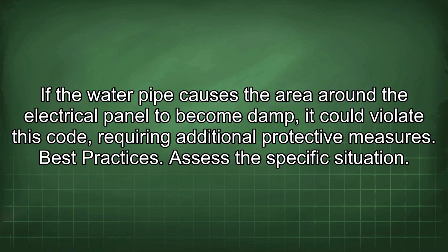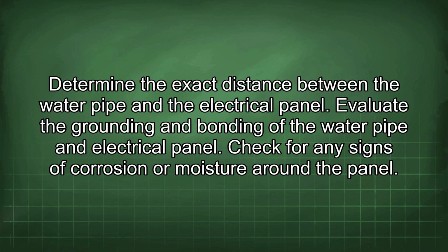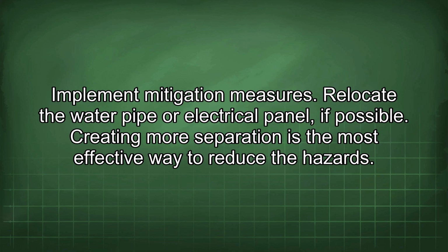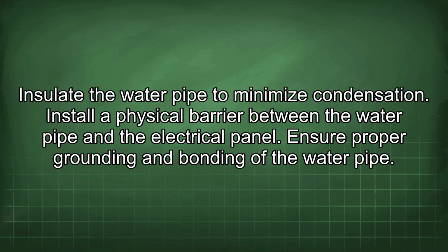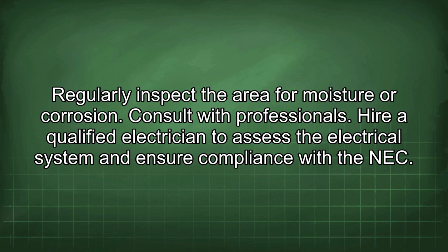Best practices. Assess the specific situation. Determine the exact distance between the water pipe and the electrical panel. Evaluate the grounding and bonding of the water pipe and electrical panel. Check for any signs of corrosion or moisture around the panel. Implement mitigation measures. Relocate the water pipe or electrical panel, if possible. Creating more separation is the most effective way to reduce the hazards. Insulate the water pipe to minimize condensation. Install a physical barrier between the water pipe and the electrical panel. Ensure proper grounding and bonding of the water pipe. Regularly inspect the area for moisture or corrosion.